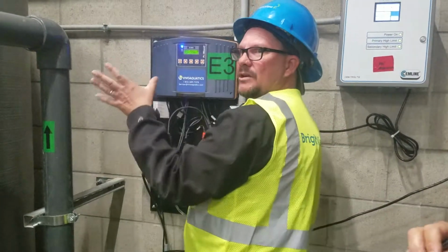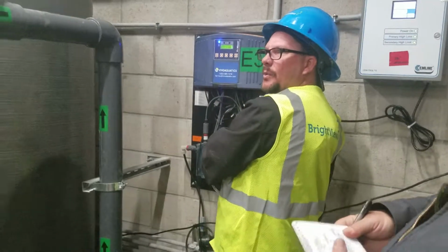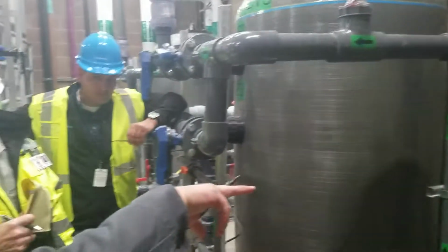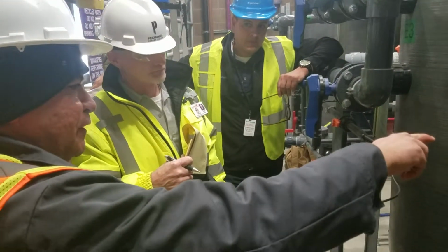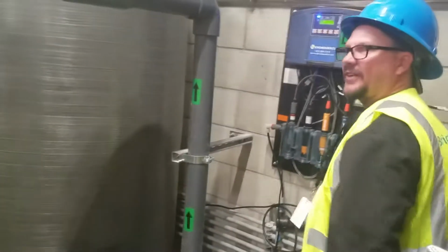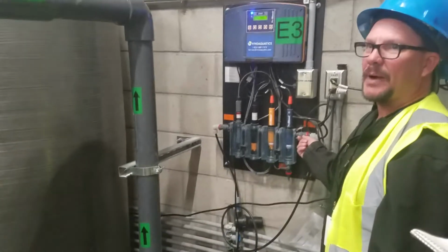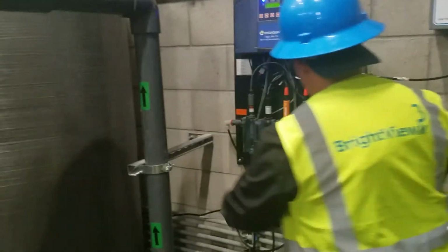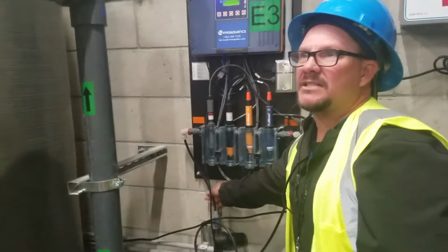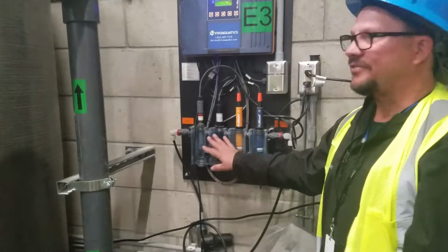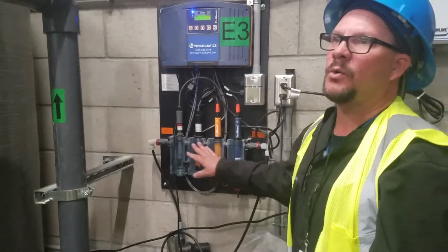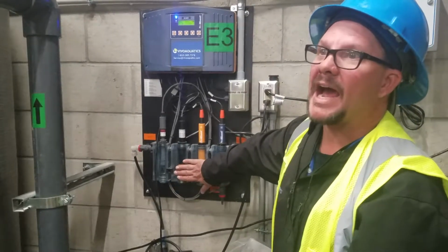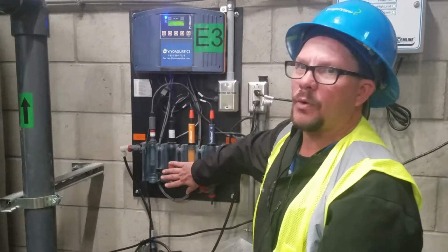Any questions right now specifically about what we've talked about with the probes and the controller, the flow parameters, and how that works? So on the outlet, you're saying it's better to keep it just wide open? Yeah, in the field, we always try to teach best practices. If we think logic here for a minute, we keep everything wide open, so you've got as much flow as that 3/8 tube will allow through this. This is one of the only low flow sample cells on the market where we're able to get a really accurate reading based on slowing the water down.